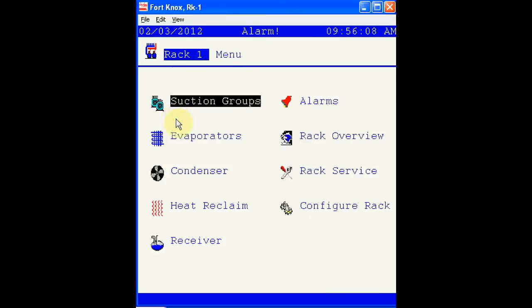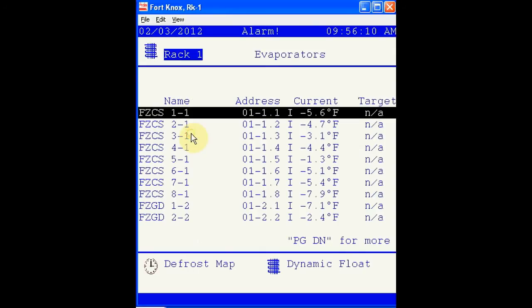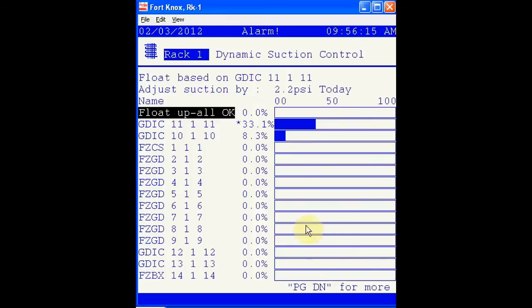Let's view the dynamic float from the evaporator. This screen tells us that it's currently floating based on glass door ice cream case 11. We can see that today it's floated by 2.2 pounds, and so far today it's been floating on this case 33% of the day. A listing of all cases that are included in dynamic suction float are listed here.